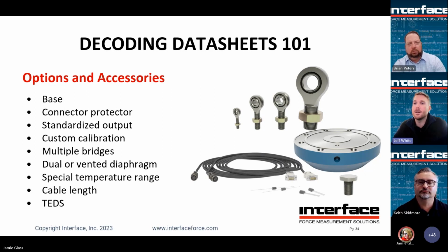Multiple bridges, a very popular option that we quote pretty often. It could be for redundancy, or if you're sending your information out to multiple data acquisitions. Dual or vented diaphragm, we will offer these options based on the environment. Are we keeping out water, or are we going into a high pressure or vacuum environment? Special temperature range. We can widen the compensated range at 0. We can even do some span adjustment.